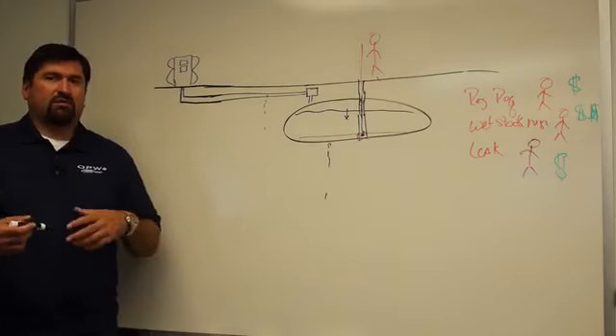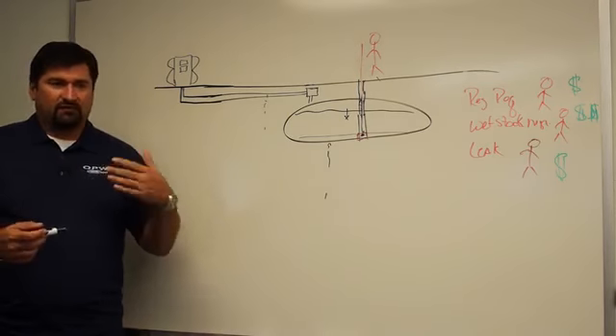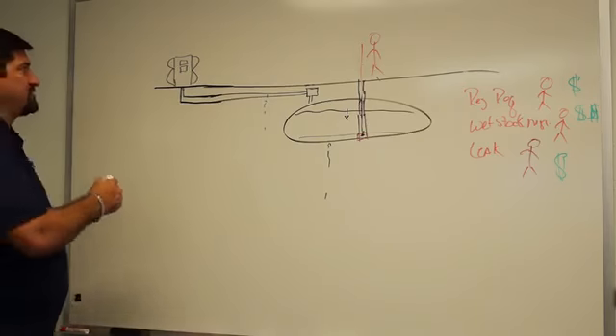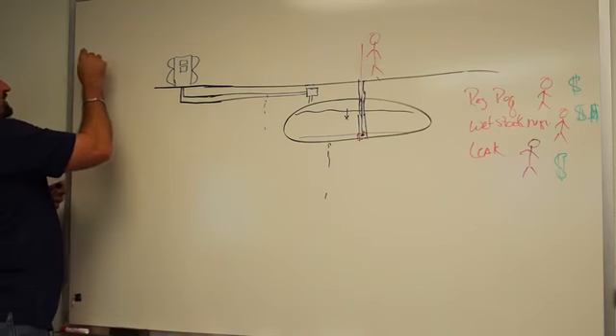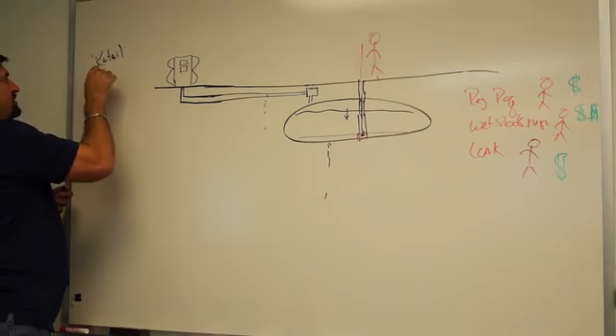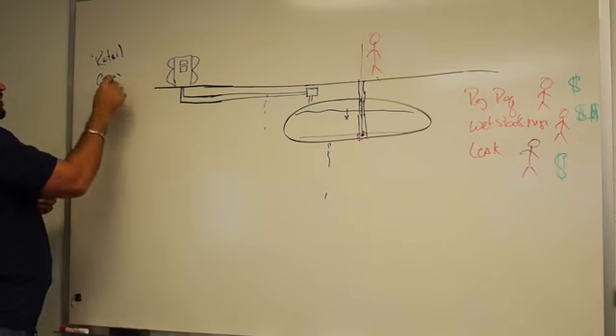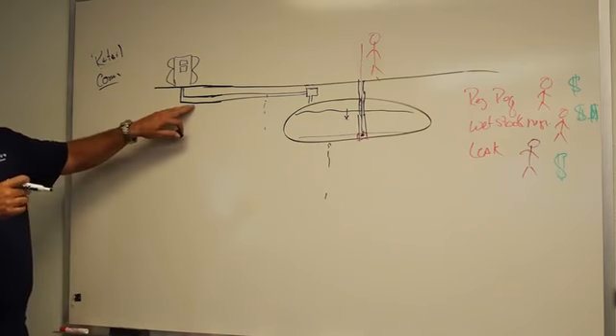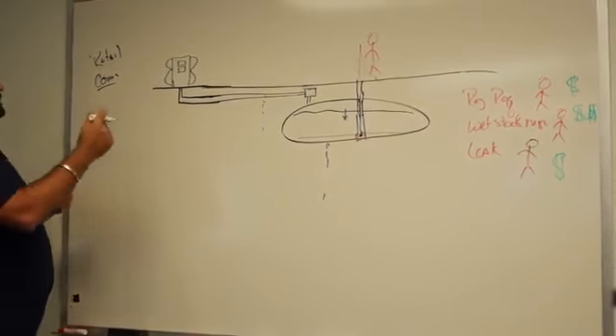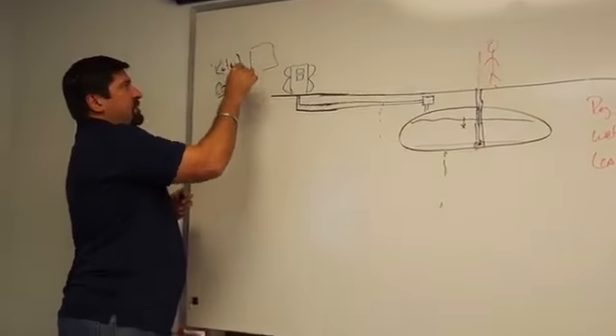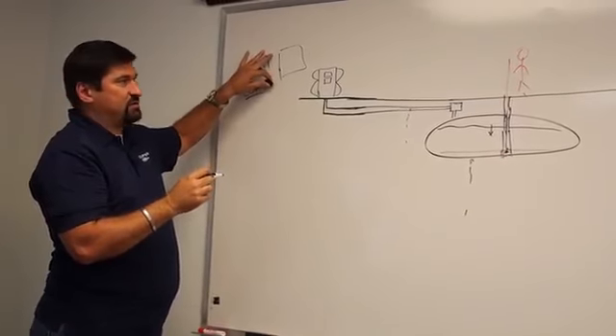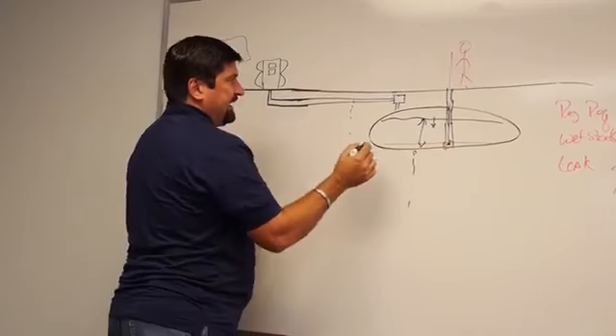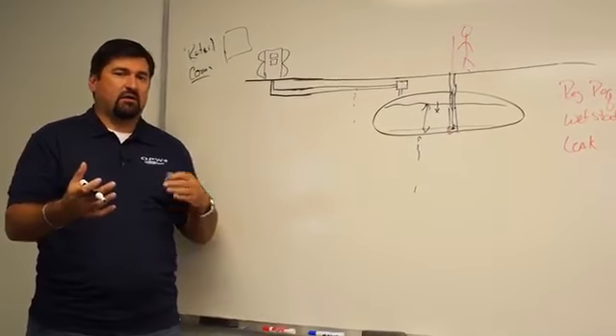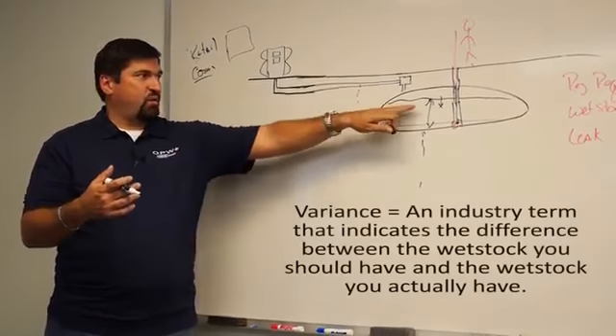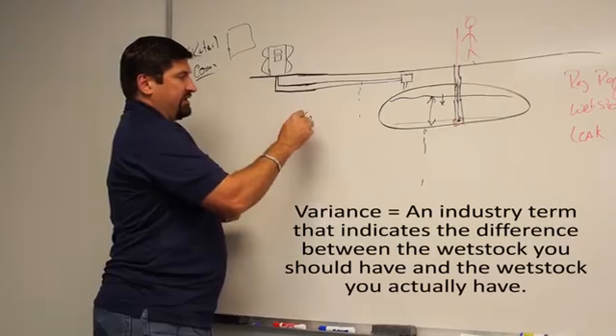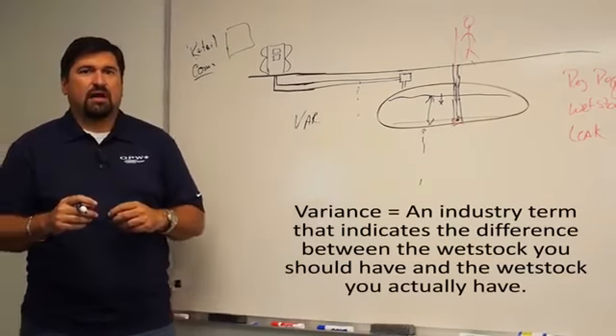If you remember in the earlier modules, we were talking about the fuel control systems at a commercial facility where you're monitoring the output of the dispenser into a vehicle. Well, in a retail or commercial location, all of this is being tracked either through a point of sale or through a local authorization. But you're monitoring what was being dispensed out of the dispenser. So if you're tying in an automatic tank gauge here, basically you're going to look at what was being dispensed, what was actually being depleted in the gauge, and then come up with the mathematical equation of what was dispensed versus what was delivered versus what is physically left in the tank. And what that will tell you is the variance for that particular product for that particular day.